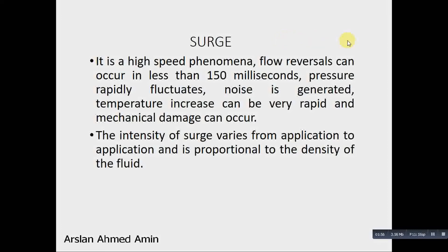Pressure rapidly fluctuates. Noise is generated. Temperature increases. It can be very rapid and mechanical damage can occur. The intensity of surge varies from application to application and is proportional to the density of the fluid. So greater the density, greater the surge and greater the damage.